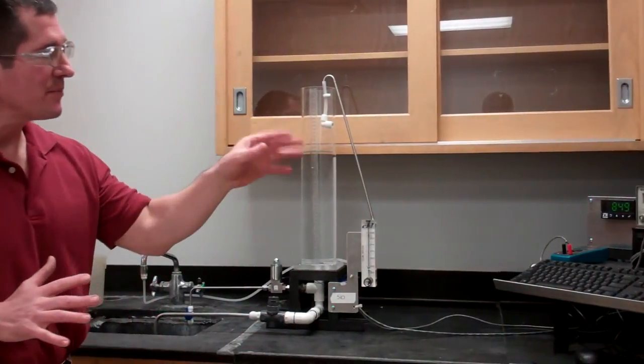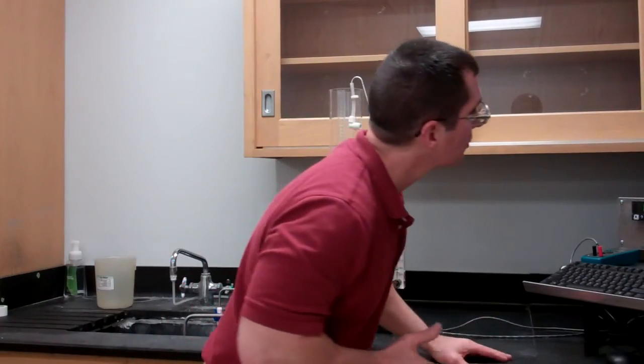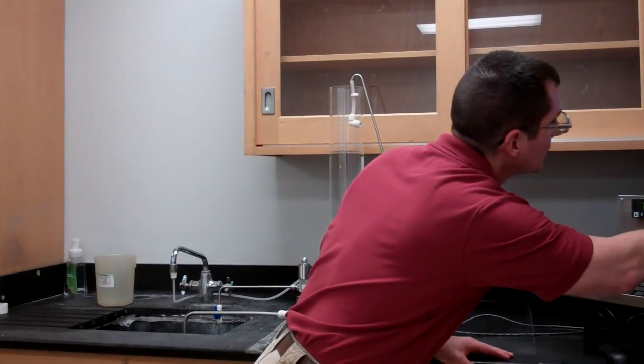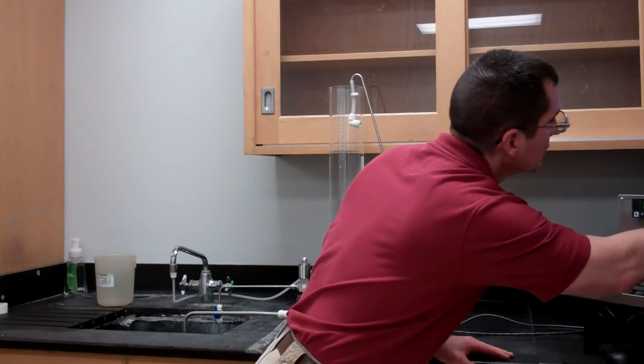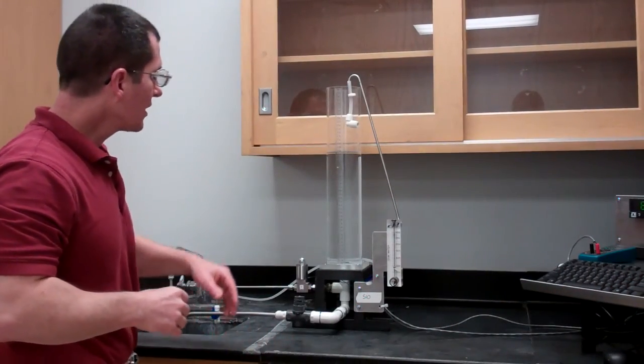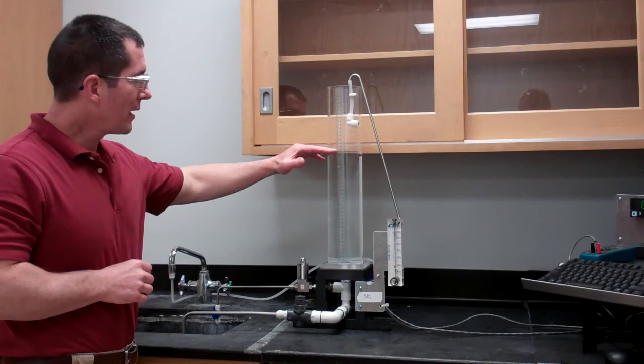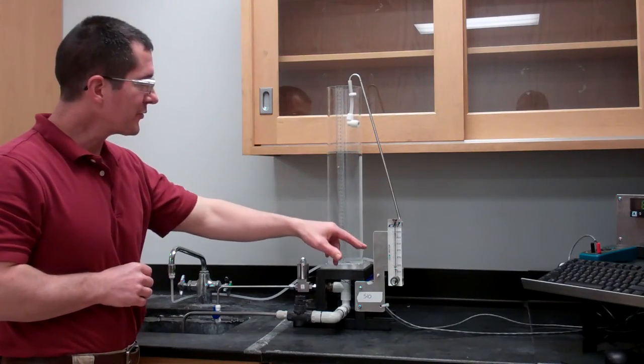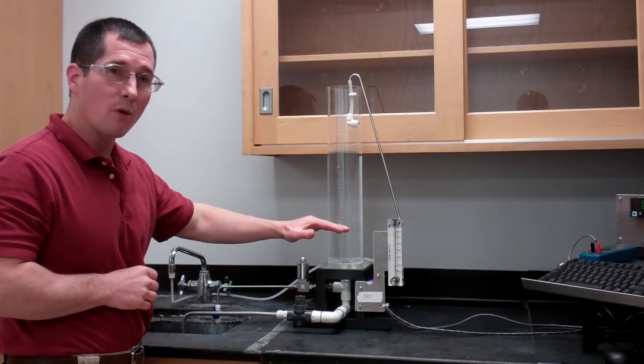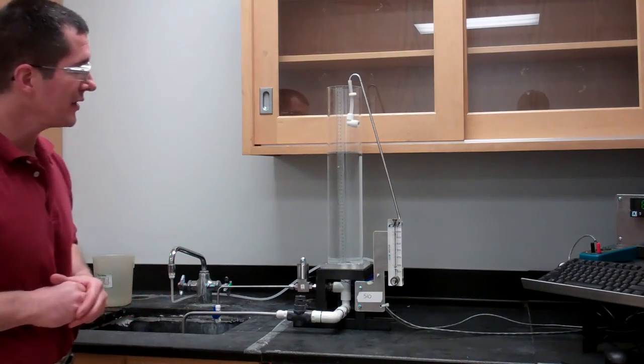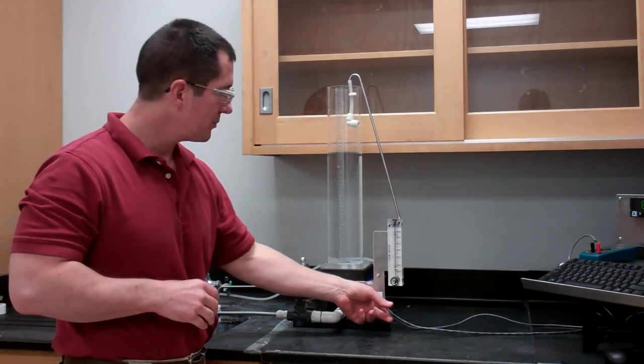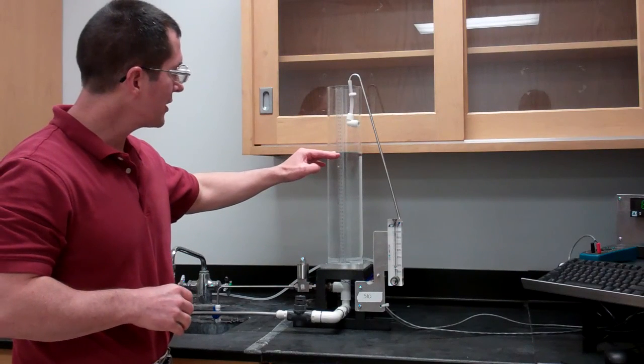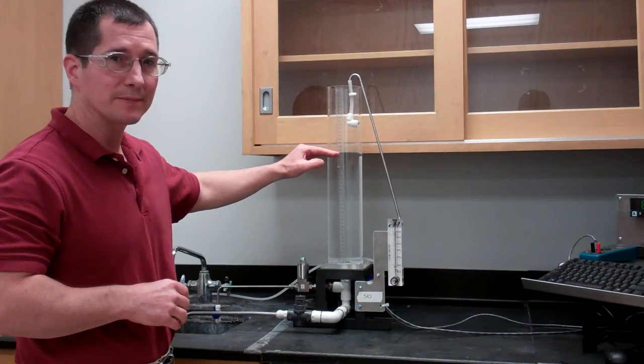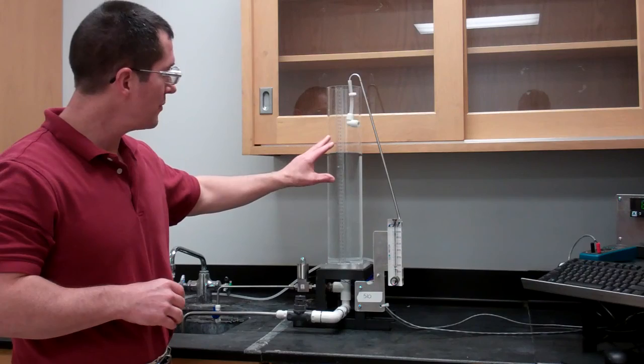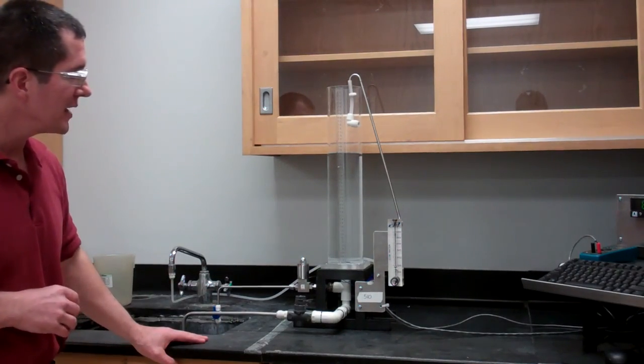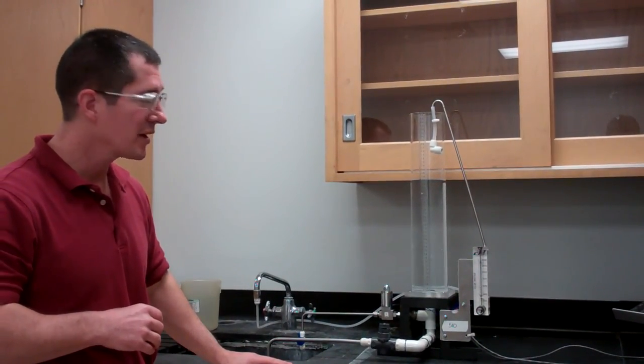But is that same input signal, let's say right now I've got it set to 15 volts, going to give the same flow rate at a different height of water in the tank? That's something you're going to investigate. So you're going to calibrate the pressure transducer, and you're also going to characterize the final control element. Those are the two main parts of experiment 1 that you'll do with experiment 510.